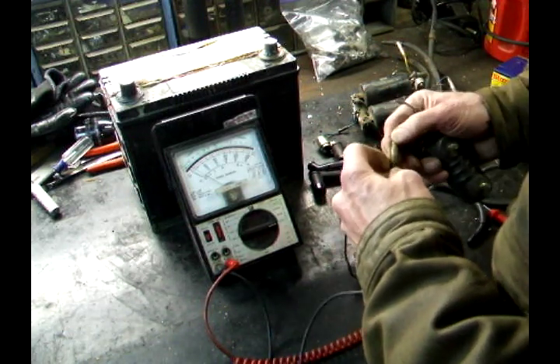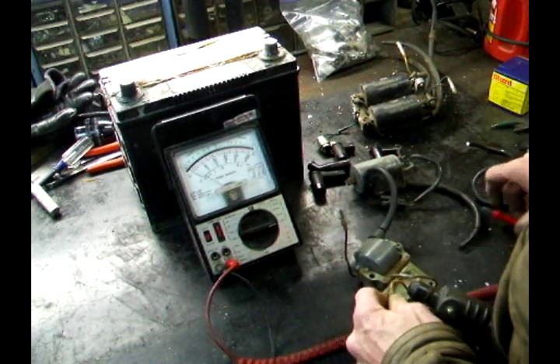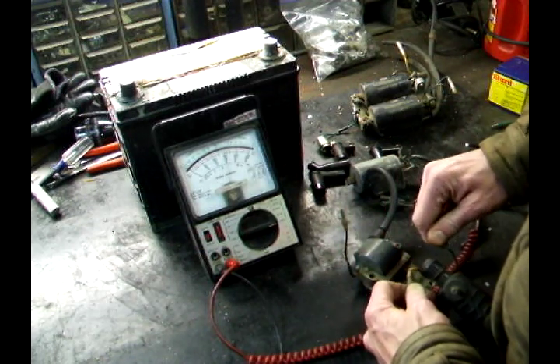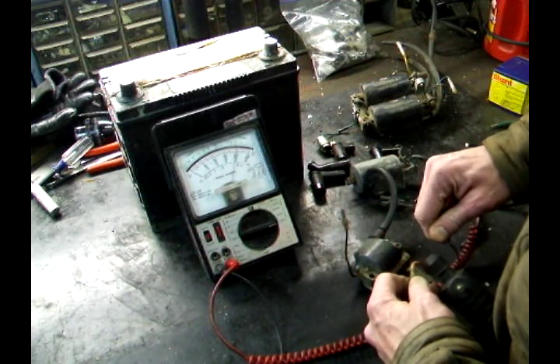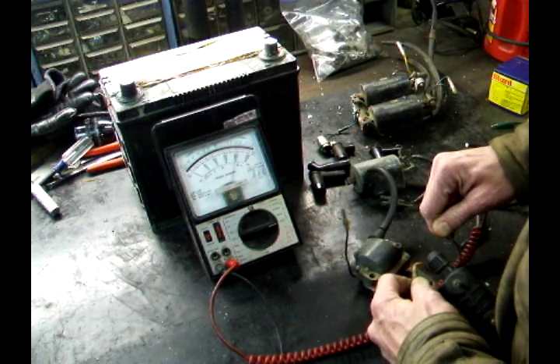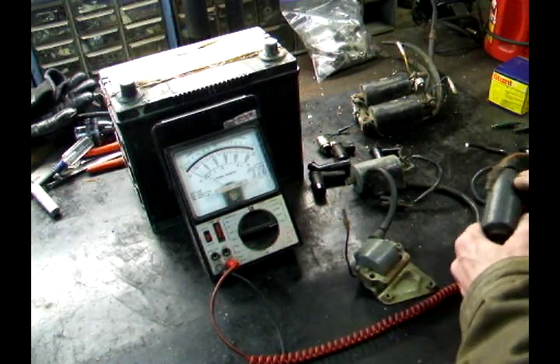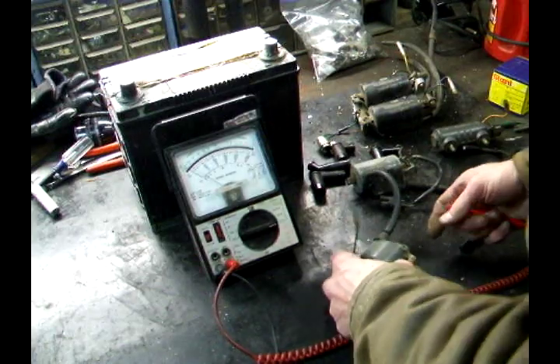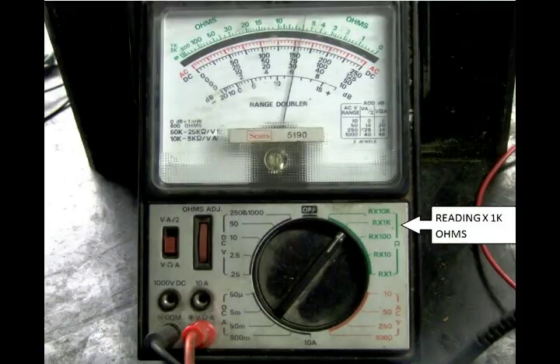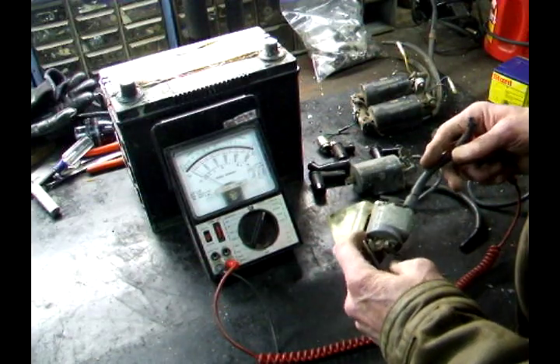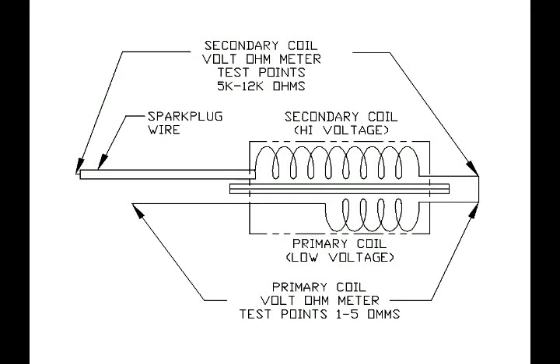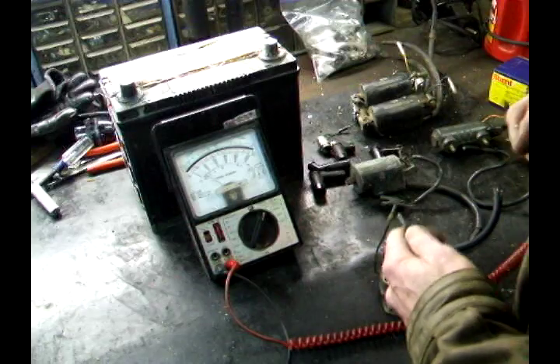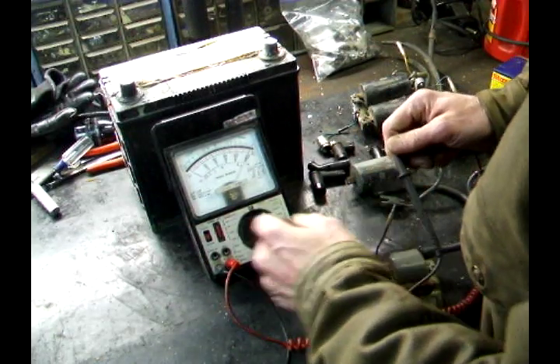And then measure across. And this one's about 2.5 ohms. Then you want to change it to the reading times 1,000, because it's 5,000 to 10,000 ohms across the high voltage coil. Again, you want to zero your meter.